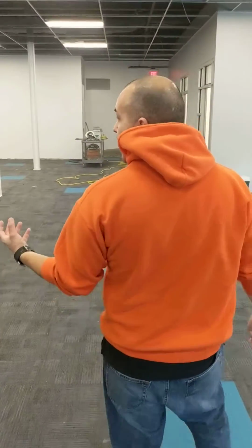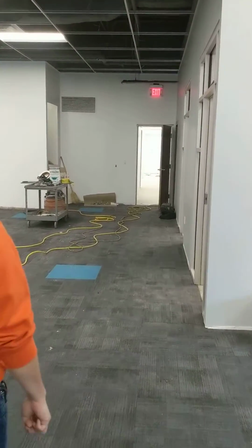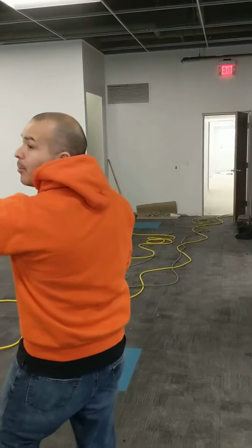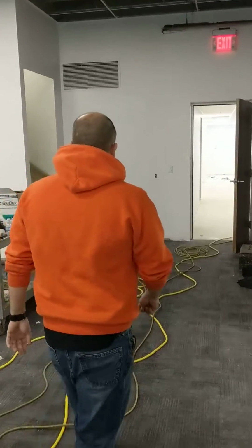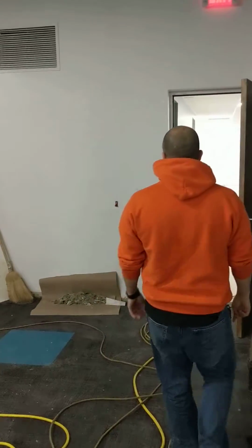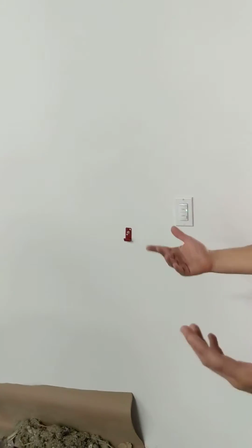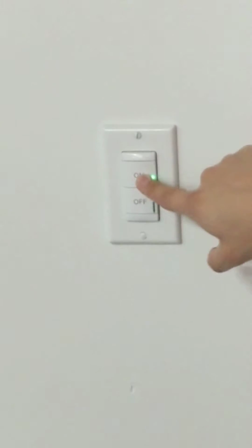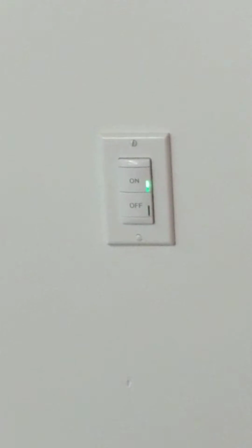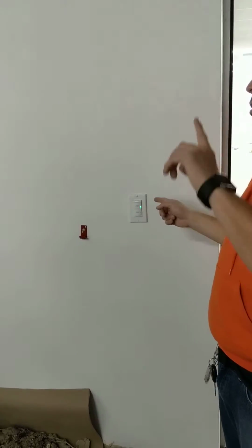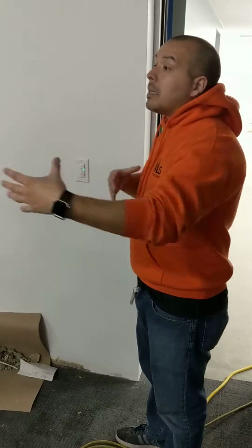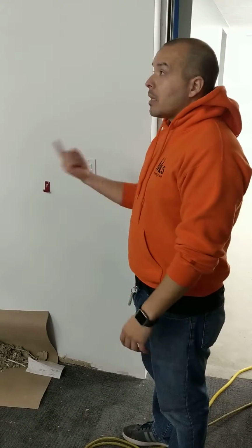What's really nice about this is the fact that all the switches are Cat 5 devices, so they're not physically hardwired to any circuit. What we do is we go in and program it and say, this Cat 5 switch you need to operate this, that Cat 5 switch you need to operate for that. Theoretically, if you wanted to, you can literally tie this Cat 5 switch to turn off and on the entire building. I mean, it'd be against code because you're turning stuff on and off, but they all work as 3, 4, or 15-way switches, however you want it to. We can program the switches, the aux sensors, and any photo cells you may have to operate either all the same things or completely different things, even though they're in the same zone.